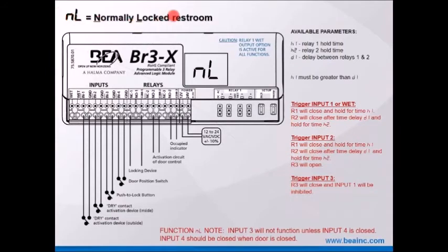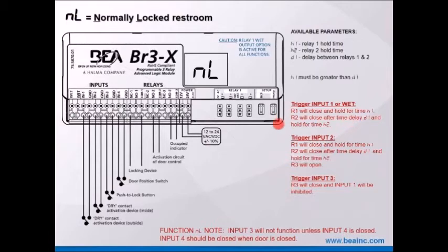NL — normally locked restroom. A dry input triggers input one and ground. Another dry input on input two and ground is for the activation device inside the restroom. Input three is a push-to-lock function, and input four is a door position switch (DPS). Triggering input one will cause relay one to close and hold for H1, relay two will close after D1 delay and hold. Relay three will open. If you trigger input three, relay three will close and input one will be inhibited.